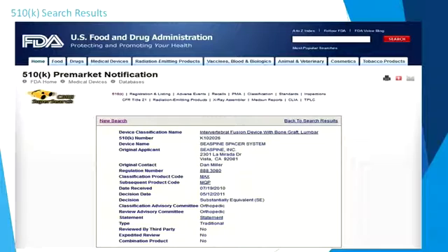You can see that they did a 510K, a traditional 510K, sort of the 4th thing from the bottom. And then finally, it's a statement. So there are 2 options, and I know Rob's going to go into this. Is Rob gone? He's going to go into this a little further. You have 2 options. You can either submit a 510K summary or a 510K statement. The statement is just essentially your indications for use and nothing else. The 510K summary is a really good summary of all the testing that you submitted to FDA to demonstrate substantial equivalence. So that becomes public.